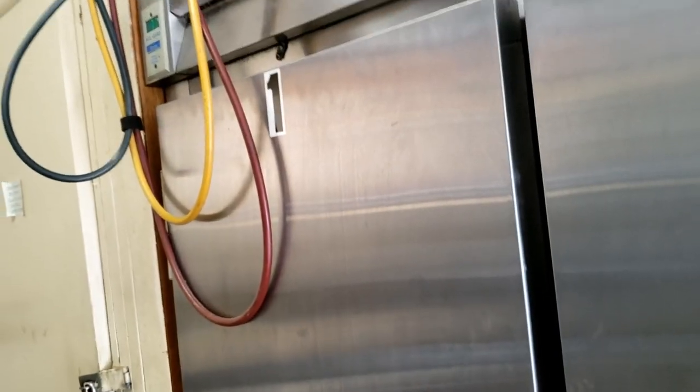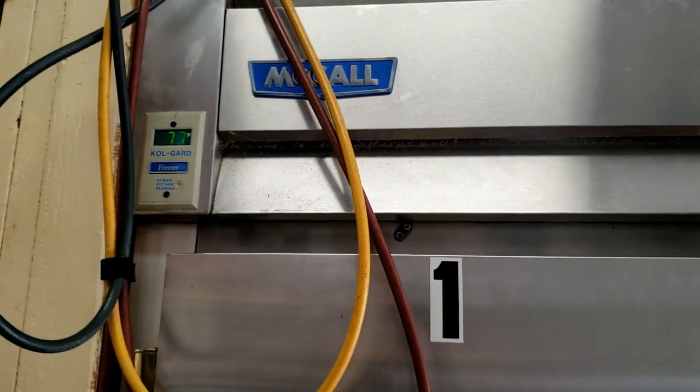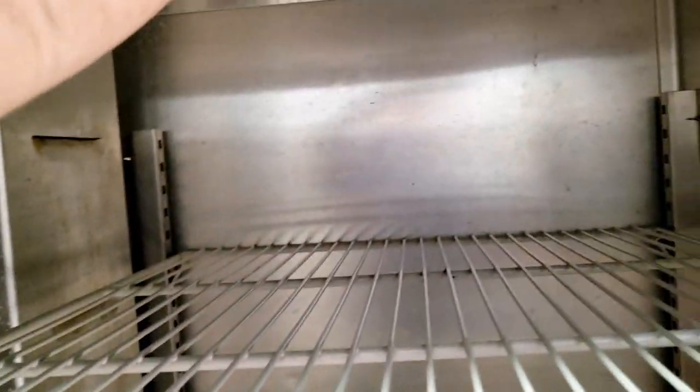The thing uses R-502, it's really really old, but it's in fairly good shape and the owner doesn't really want to replace it — he just wants to maybe replace the compressor. The question is: what all are we going to have problems with if we do this? As you can see, it's in fairly good shape. These units are expensive for those not in the industry.